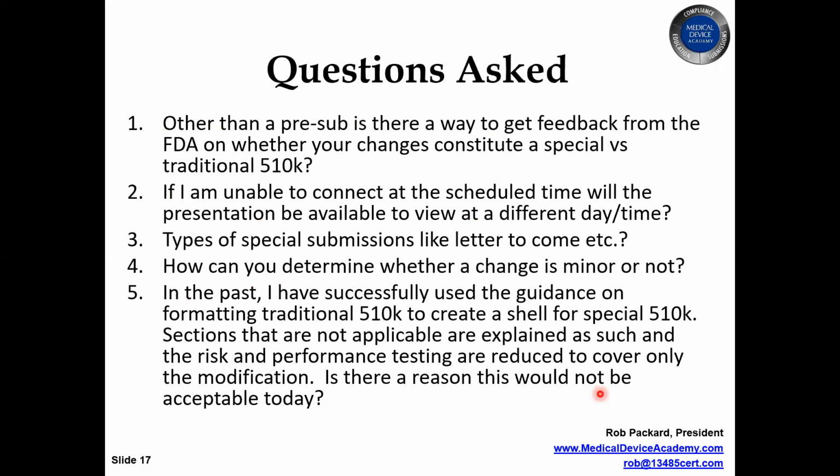So it's a question of, are you adding the new verification testing because the standards changed and the FDA implemented a new requirement, or are you implementing this new verification testing because you've identified a new risk that required additional testing? And when you have that, now we have something that needs to be addressed with a traditional 510K. Because the FDA is probably going to want to see your test protocol and the full test report.